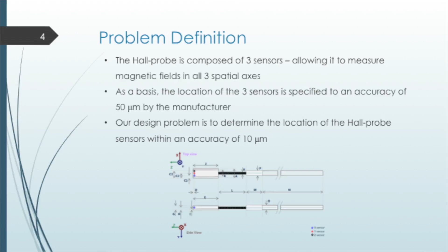So how to tackle this problem? Well, a device is required, and we call it a magnetic jig. So this magnetic jig must have 2 main functions. Number 1, it must produce a magnetic field with distinct field features for each Hall probe sensor and in each axis. And what this means is that it allows us to relate the position of the Hall probe sensor itself to the magnetic jig. And then its other function must be that it should accommodate ball-mounted retroreflectors to allow the determination of the location of the magnetic jig with respect to the insertion device.